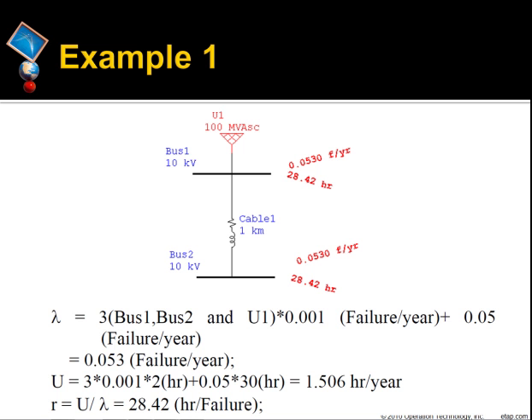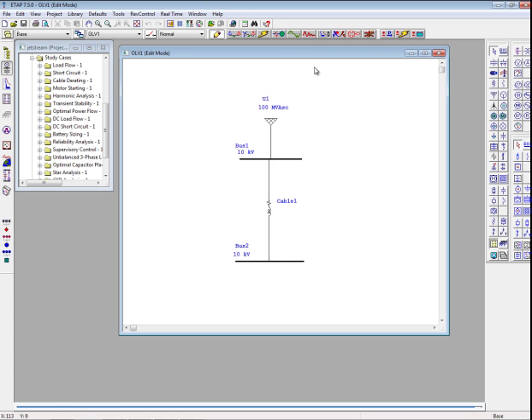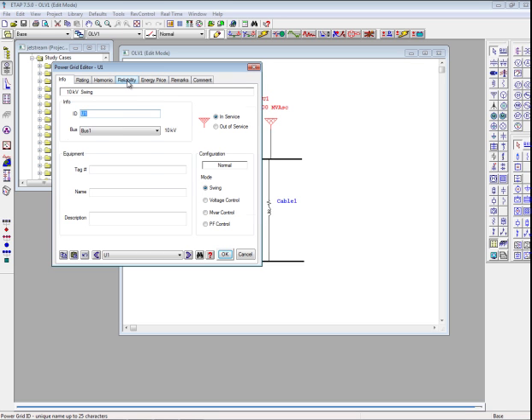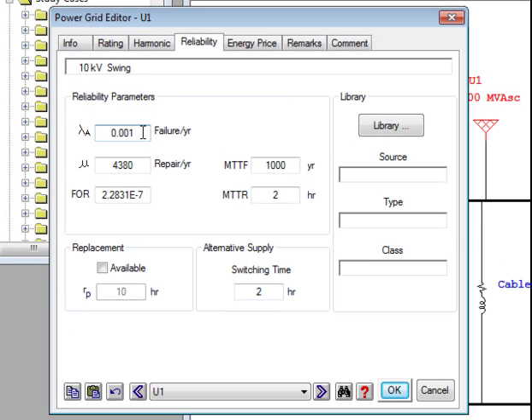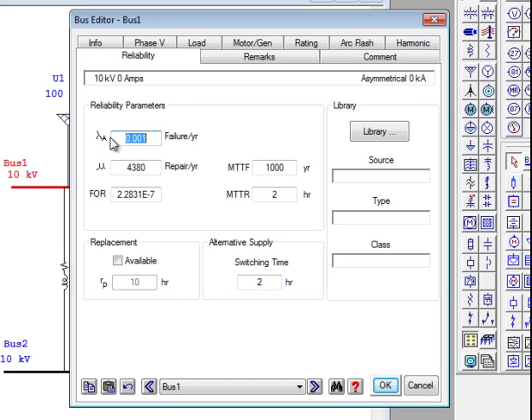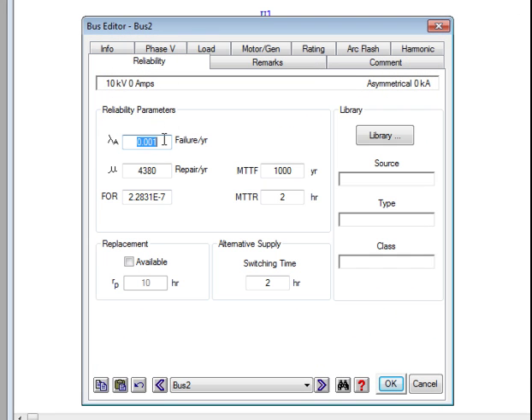I will go to ETAP to open this example and show the calculations. I open Example 1, which I previously created, in ETAP. I go into the utility editor by double clicking on it. If I go to the reliability page, I can see that the failure rate is set to 0.001 failures per year and MTTR is set to 2 hours. I select OK, and for bus 1, going to the reliability page, the failure rate was set to 0.001 and the MTTR was set to 2 hours. For bus 2, in the editor going to the reliability page, the failure rate was set to 0.001 and the MTTR to 2 hours.